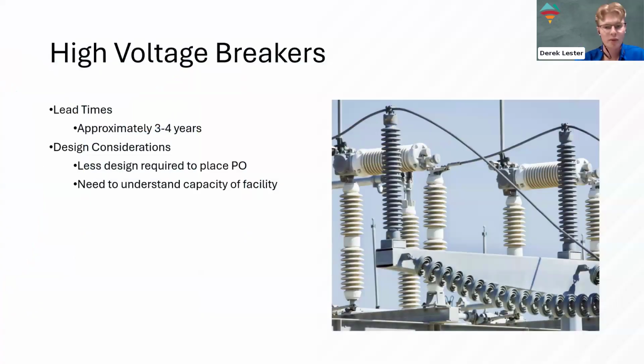The first category of equipment we'll talk about is high voltage breakers, on the transmission and distribution side of the fence of the project. These items are looking at about a 3 to 4 year lead time from issuing of PO, and the variance in that range correlates to the voltage of the breakers. If you're looking at 230 kV or slightly lower, you're looking at about 3 years, and if you get up to about 500 kV, you're looking at about 4 years.